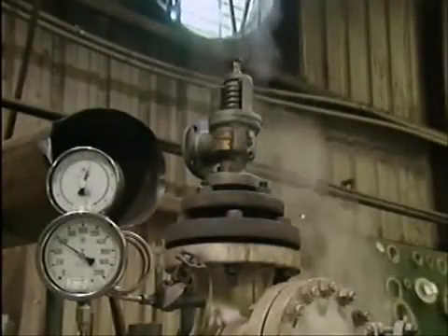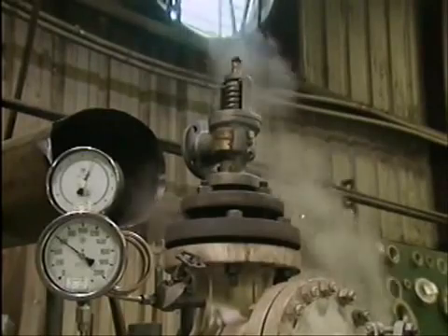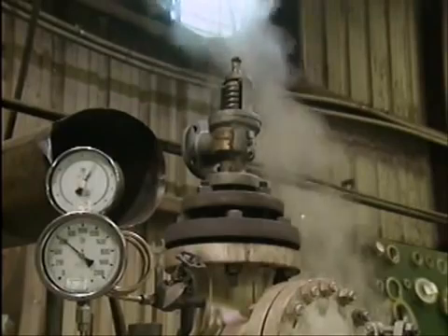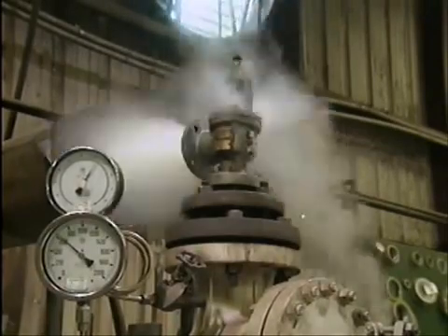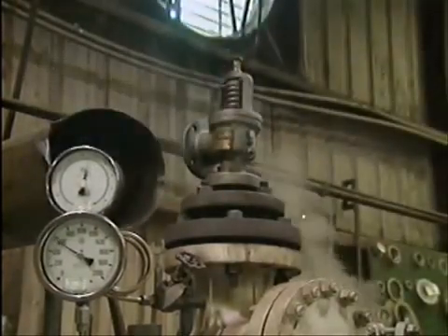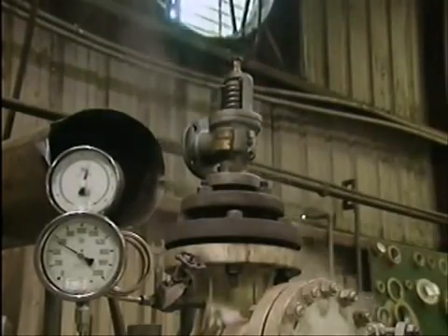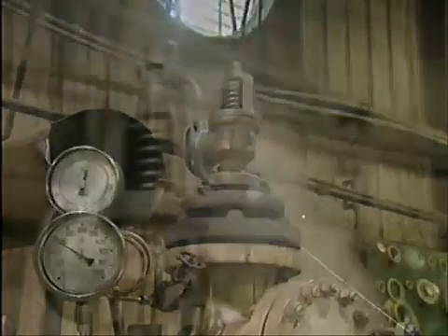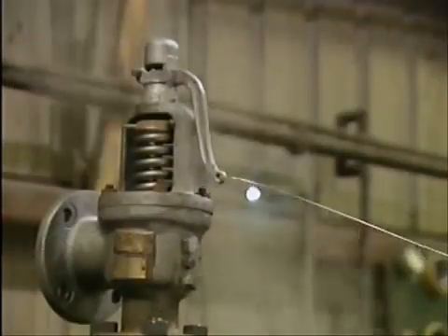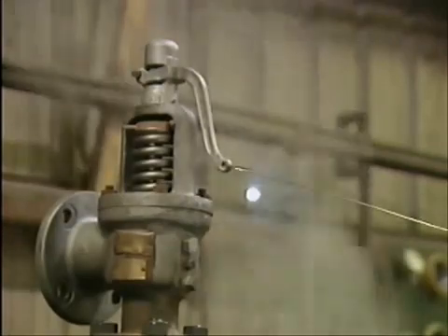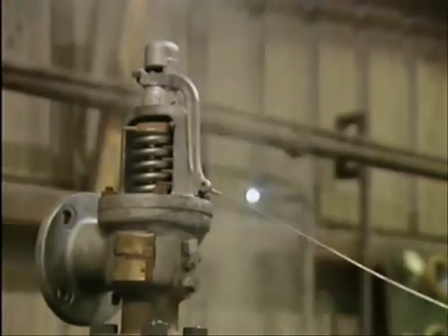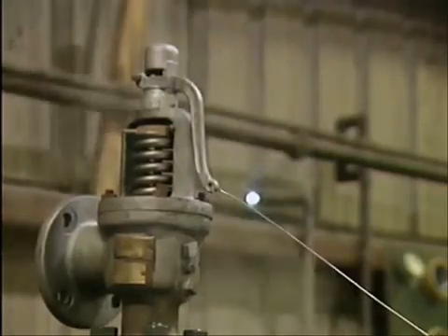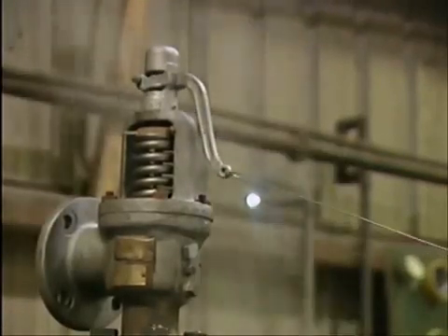An external inspection may reveal that a valve is leaking between the disc and the seat. This could occur if the valve didn't reseat correctly after the last time that it popped. Or it could be caused by foreign matter, such as ash, dirt, or rust particles trapped between the seat and the disc. In many cases, you can correct either of these 2 causes of leakage by manually lifting, or hand lifting, the valve.